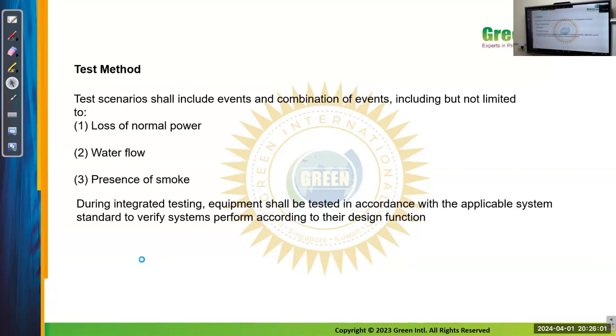So, test methods. Test scenarios shall include the events and combination of events, including but not limited to. So these are all the important terms, but it is not limited to only these. Loss of normal power: they will test if there is any power loss, whether the emergency power supply is working or not. And water flow: for the sprinkler systems, whether proper water flow is available or not. And presence of smoke: if there is any presence of smoke, whether the detector is working or not. So these are all the main things they will test in the event of any risk or any fire.